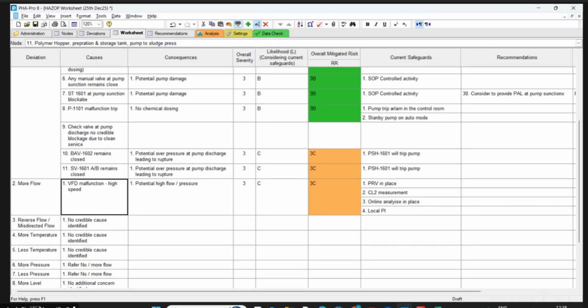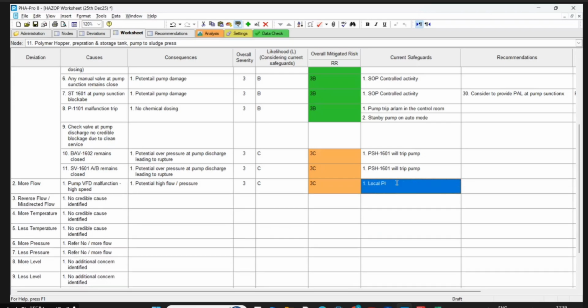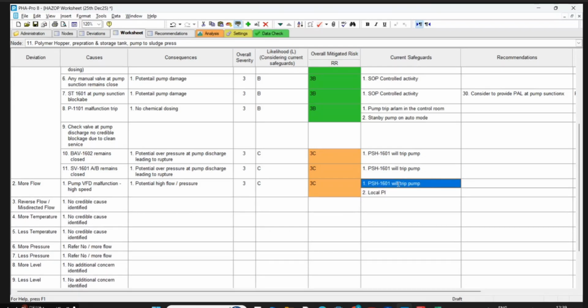Okay, now if the VFD malfunctions at full running, how do you control potential high flow, high pressure? It will develop pressure, no? If the VFD is working at full speed, the pump is running at high speed. It will discharge into the flow closure chamber of the screw press. It depends on the SV. If the SV is not opening correctly and the VFD is running full, then you have a torque switch here, no? Torque switch, yeah.